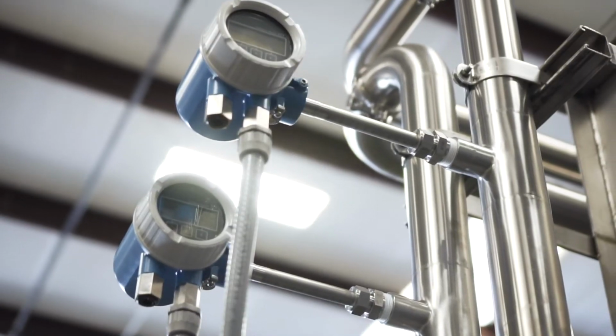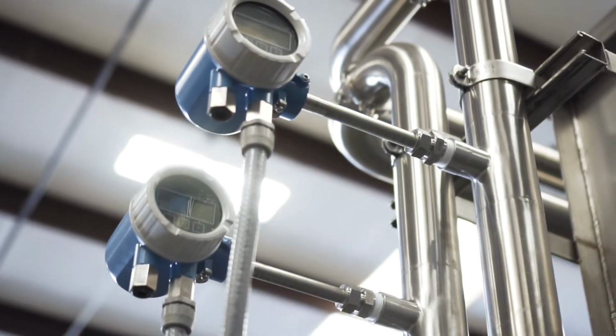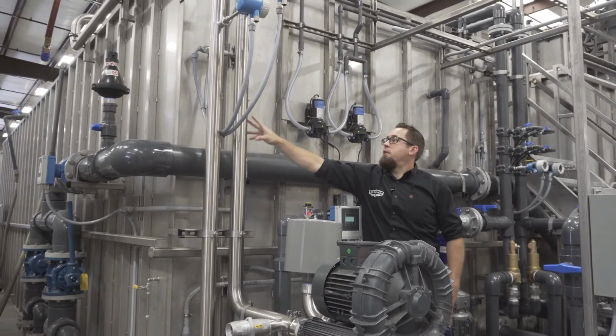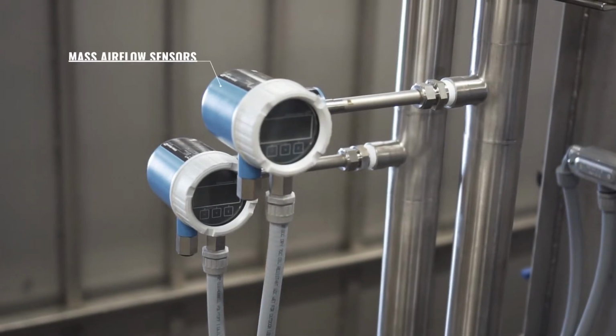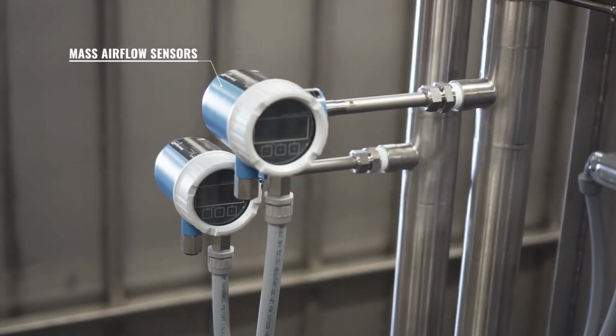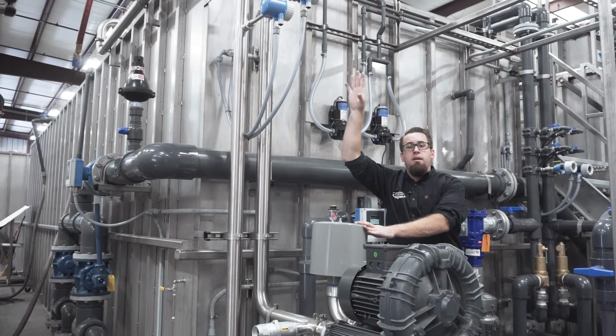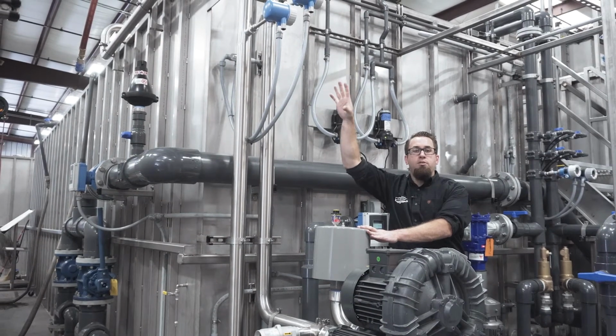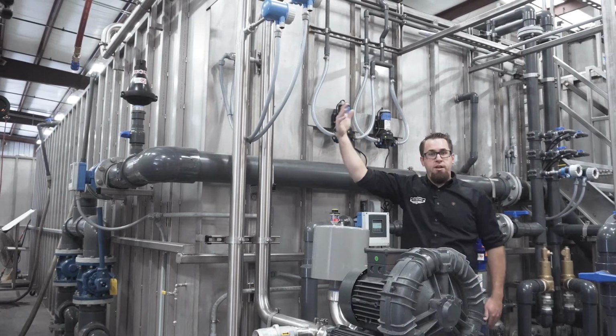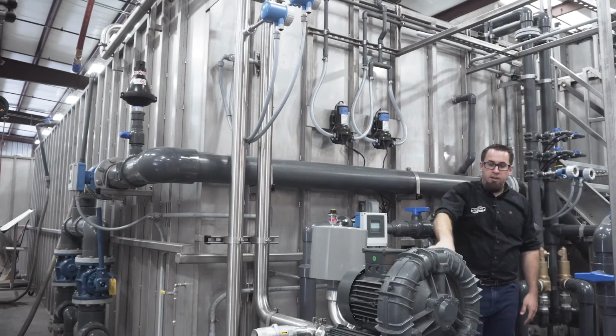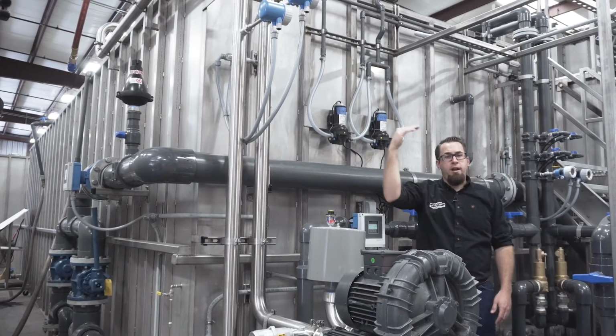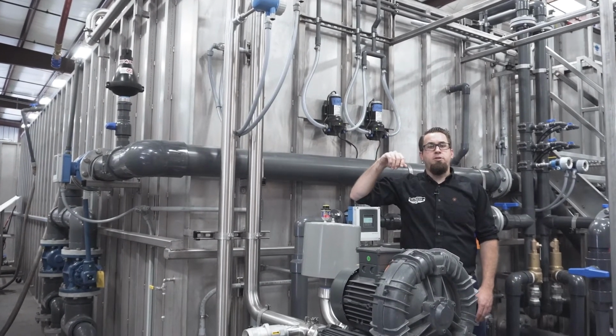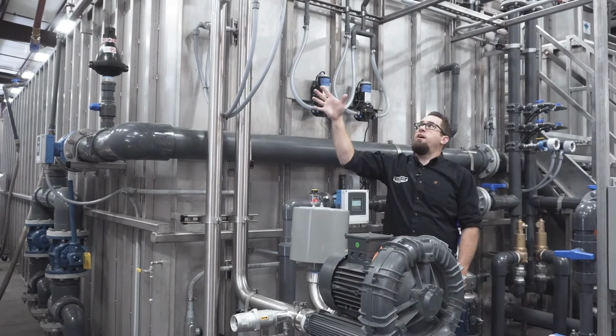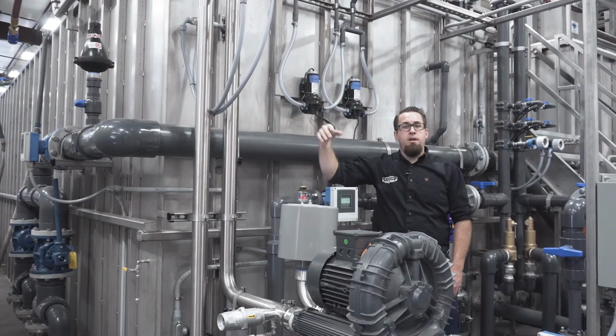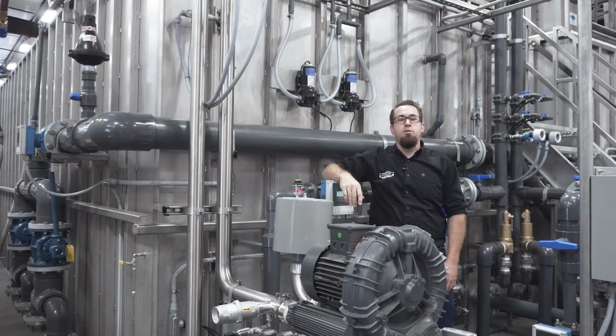The next feature that we provide for all of our municipal spec systems is a mass airflow sensor. You'll notice on the actual discharge for the membrane air scour blower that there are sensors which read the actual CFM that goes out to the membranes. This allows us to trend it and make sure that the VFD is actually corresponding with the correct flows for that particular permeate range. This also allows us to provide data back to the membrane manufacturer in the event that anything were ever to occur.